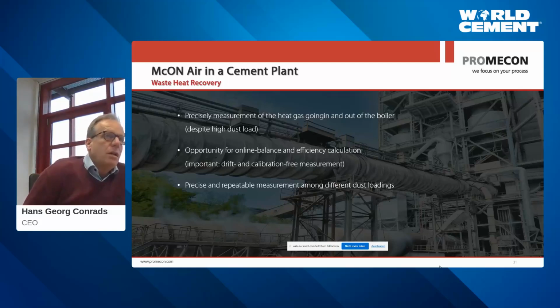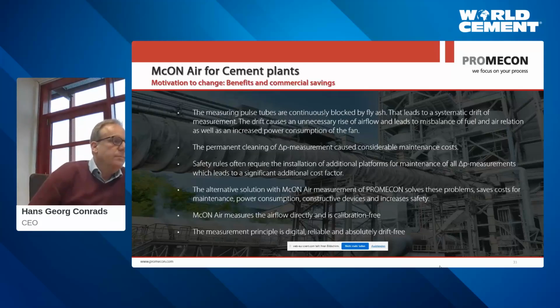In most boilers, people measure temperature, but you're missing the flow, right? In coal boilers, you can also measure the O2. So you measure the O2 level, and that tells you about the stoichiometry. But in a waste heat recovery boiler, you are not combusting anything. There's no combustion. So the typical O2 measurement that helps you to check the efficiency of your waste heat recovery boiler is not helping you. The only thing that's helping you is temperature and the flow. Because temperature and flow give you the enthalpy that goes into the boiler and the enthalpy that goes out of the boiler. So you can see how much energy the boiler has been able to get out of the waste heat gas.